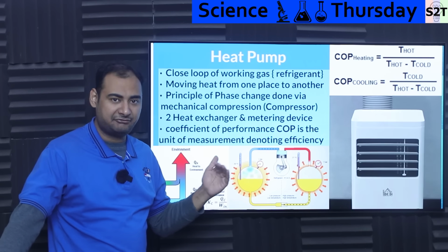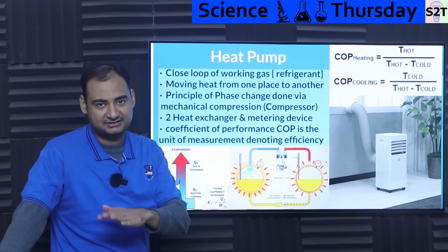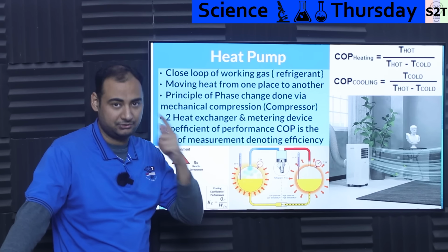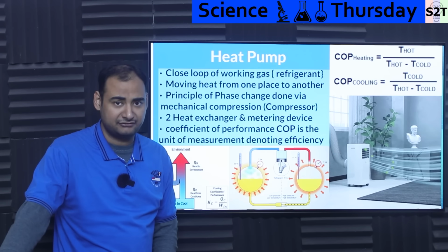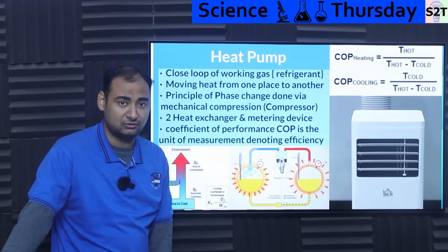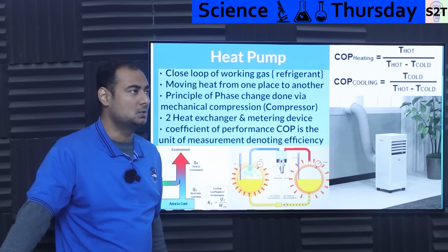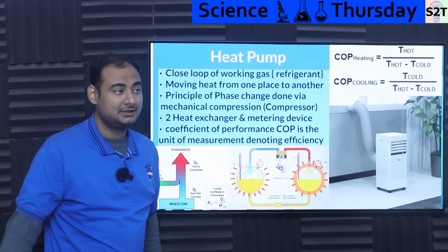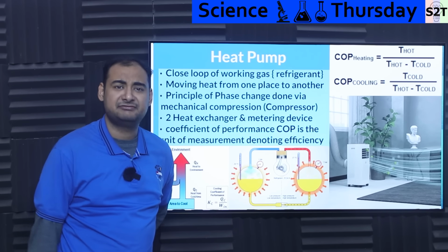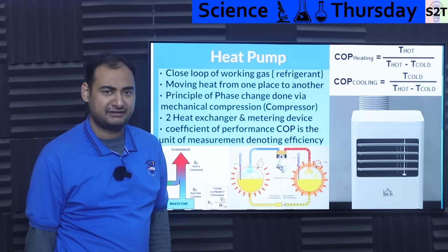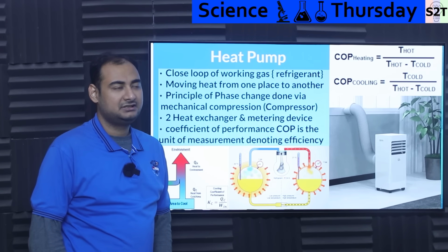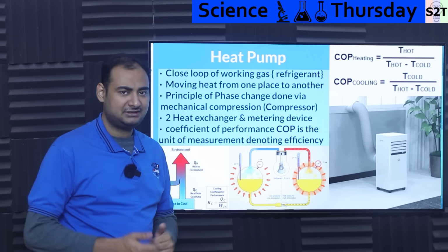For example, lift. Here the lift is basically what is the T delta you want to create between indoor and outdoor. So for example, if outdoor is very hot, 50 degrees Celsius, and you want indoor to be very cold, let's say 10 degrees Celsius, your compressor is gonna poop itself. But if, let's say, outdoor is not that hot, 35 degrees Celsius, and indoor you only want 25 degrees, that's a 10 degree delta T. Your AC is like, I got this, I can do that.